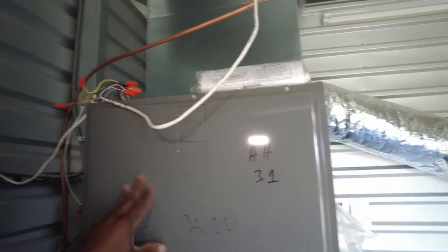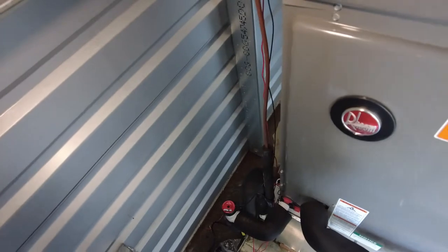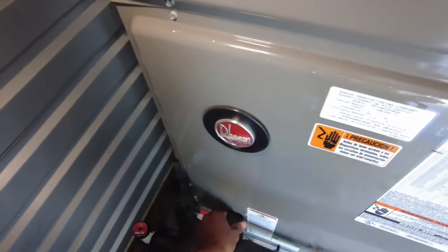All right, so I'm just over here at a call here at a storage facility and I just got done cleaning out the p-trap. It was clogged up. Now the unit's kind of short cycling, so I'm about to check voltage here and see what I've got.